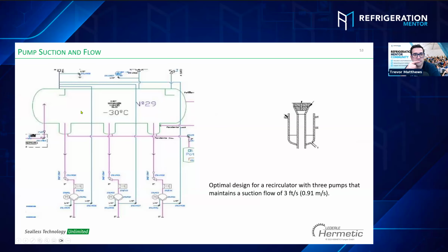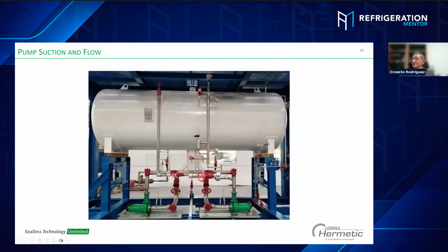Okay, we're talking about a horizontal vessel. It's the same way. We have the pump, we have the vortex breaker, and a way to collect dirt or oil, and it's very friendly. This is a typical installation for CO2. We have the vessel and each pump. For example, we have the elbows right here. We were talking about elbows before. See the distance between the elbow and the suction of the pump?